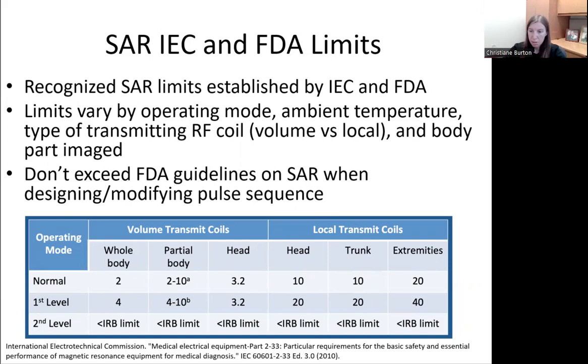The first level controlled operating mode is defined as the one where certain imaging parameters may cause physiological stress, such as peripheral nerve stimulation or tissue heating. Active medical supervision is required to use this mode to ensure that a careful assessment of benefits versus risks has been made.